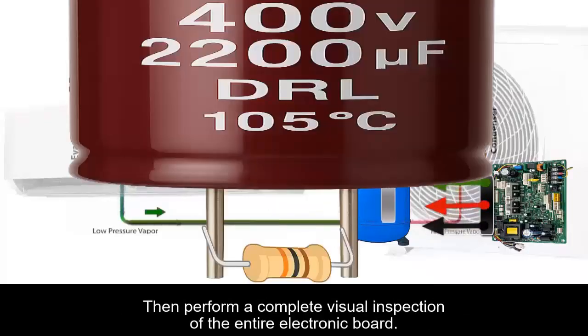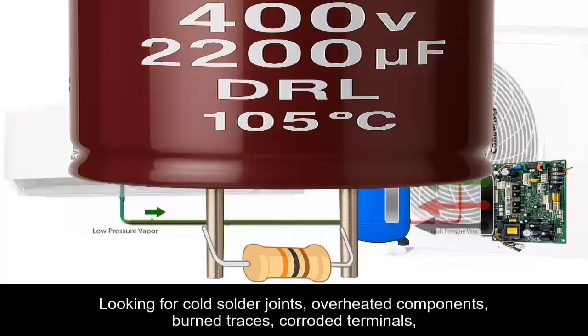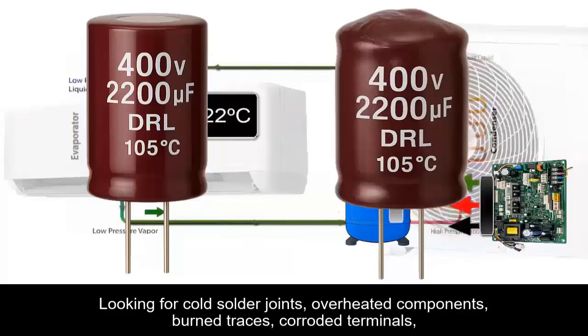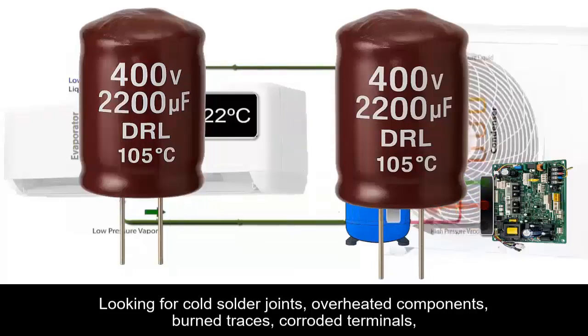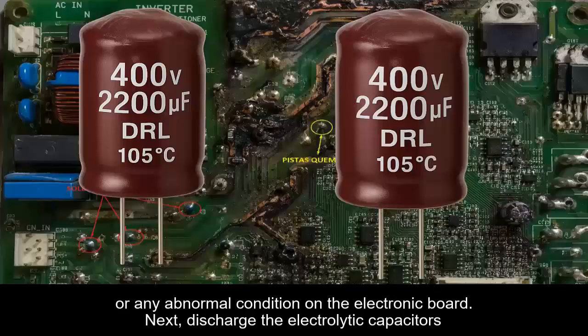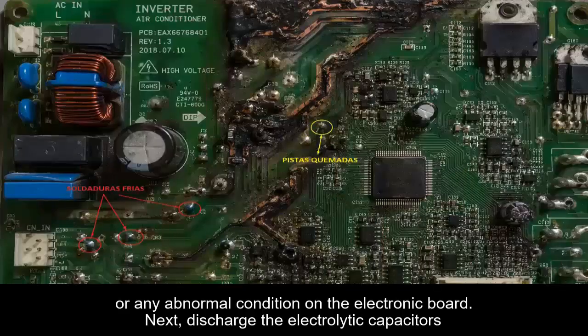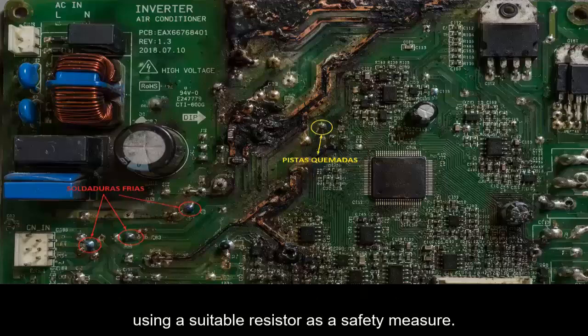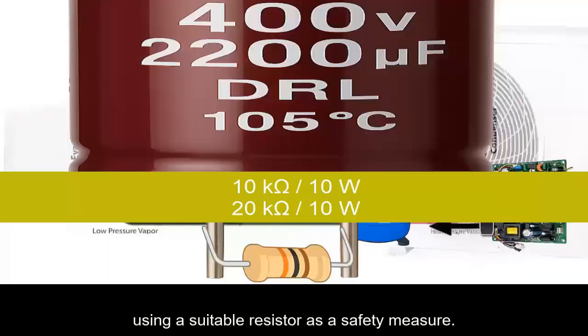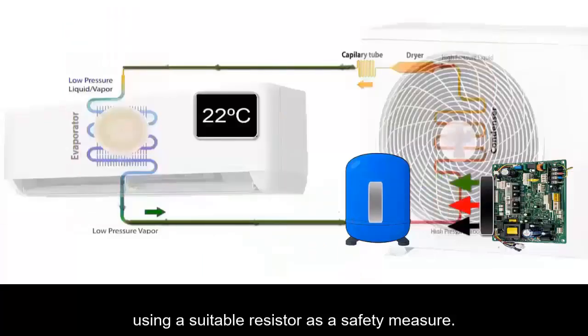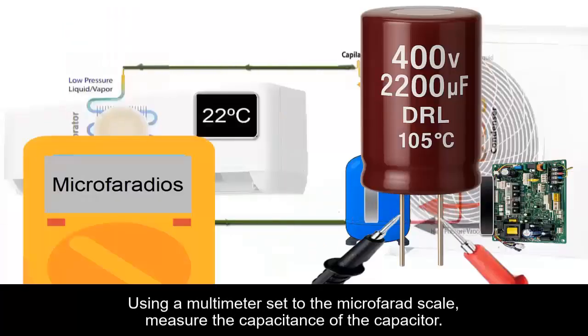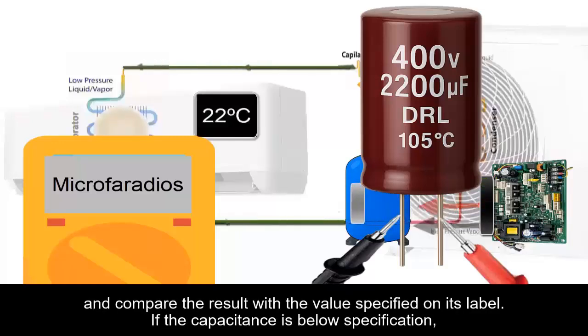Then perform a complete visual inspection of the entire electronic board, looking for cold solder joints, overheated components, burned traces, corroded terminals, or any abnormal condition on the electronic board. Next, discharge the electrolytic capacitors using a suitable resistor as a safety measure. Using a multimeter set to the microfarad scale, measure the capacitance of the capacitor and compare the result with the value specified on its label. If the capacitance is below the specified value, the electrolytic capacitor must be replaced.